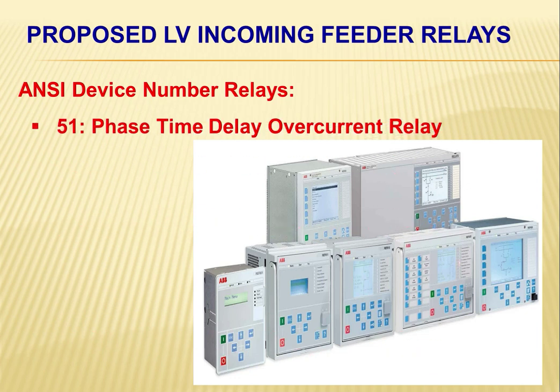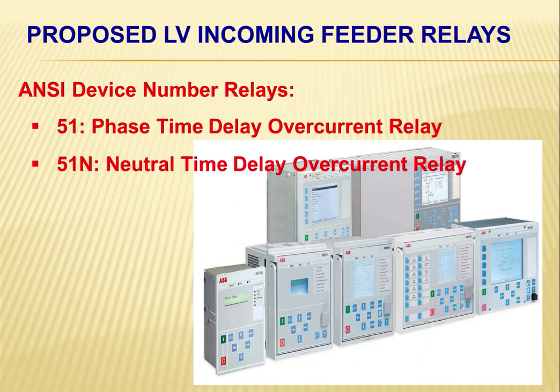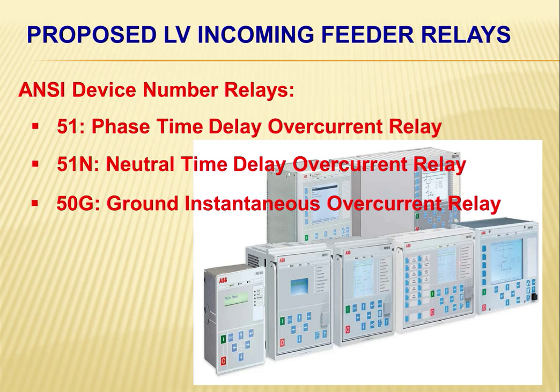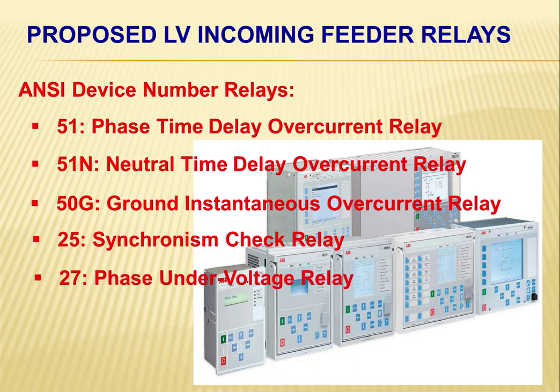The first one is relay 51 or the phase time delay overcurrent relay. Relay 51N, the neutral time delay overcurrent. 50G, the ground instantaneous overcurrent relay. 25, the synchronism check relay. We have this synchro check relay because in our single line diagram, we have both bus A and bus B, and we have the bus coupler. There is a tendency or situations that both bus A and bus B will be synchronized, or both source 1 and source 2 will be connected in parallel. And we have also relay 27 for the phase undervoltage.